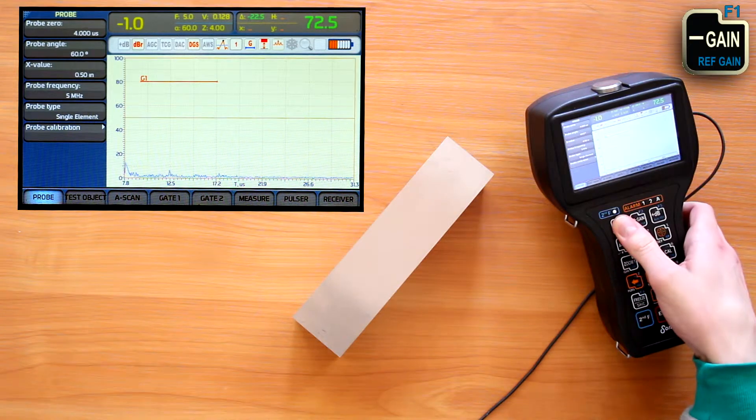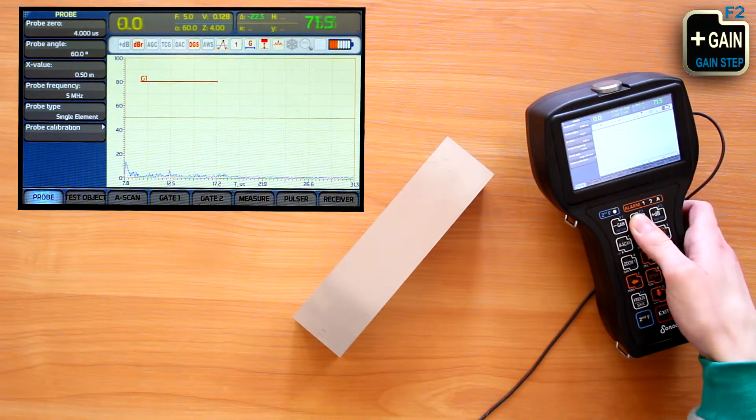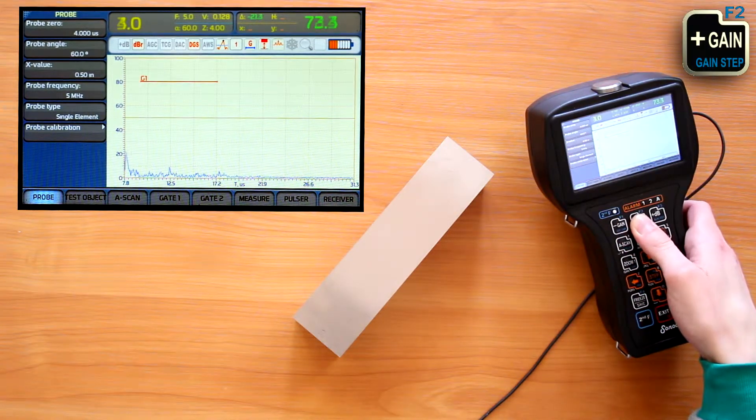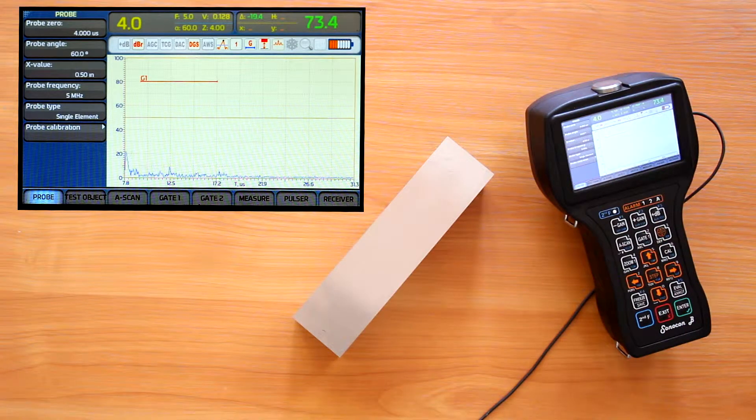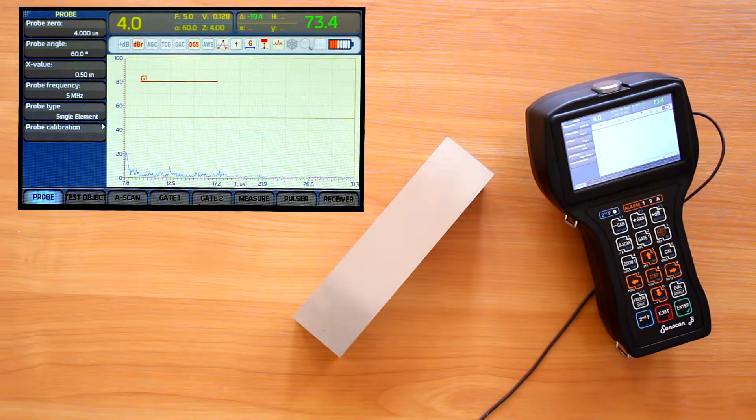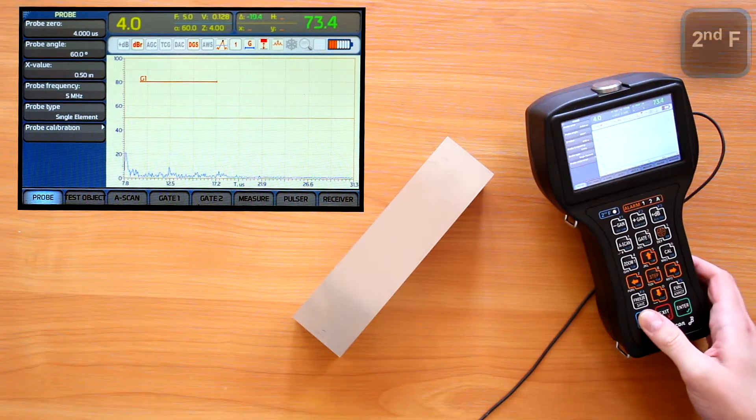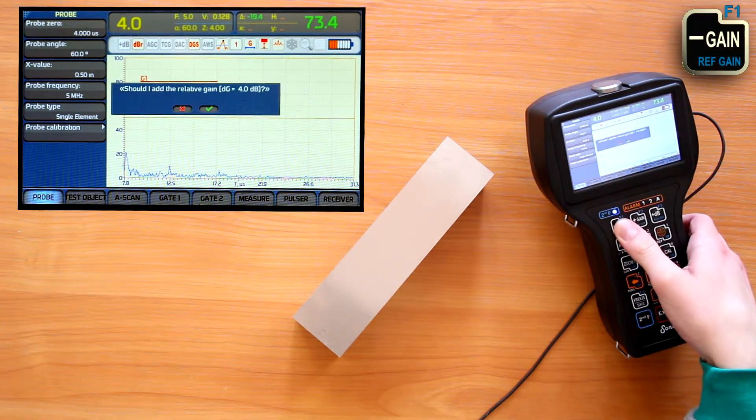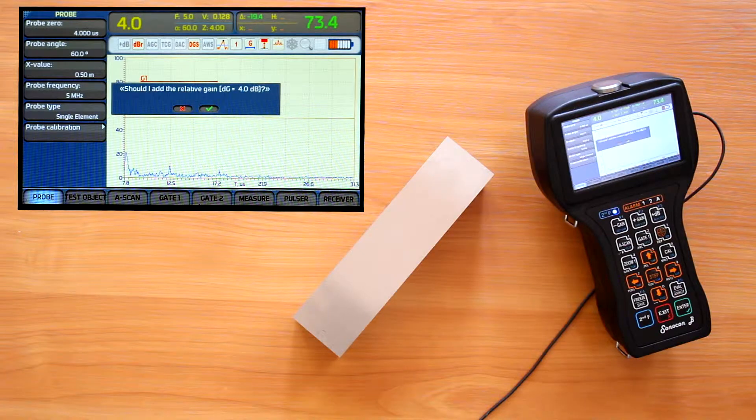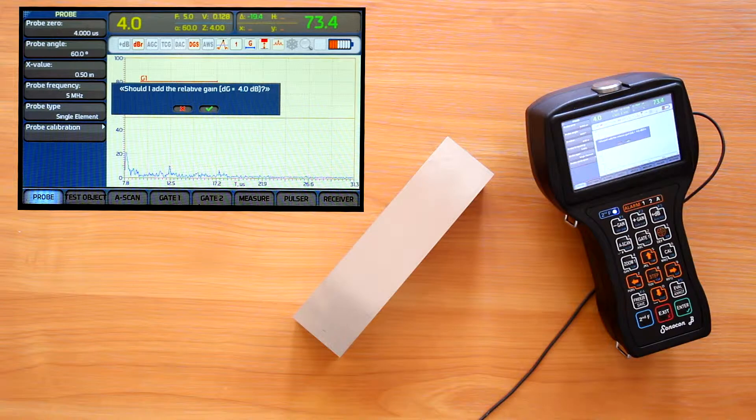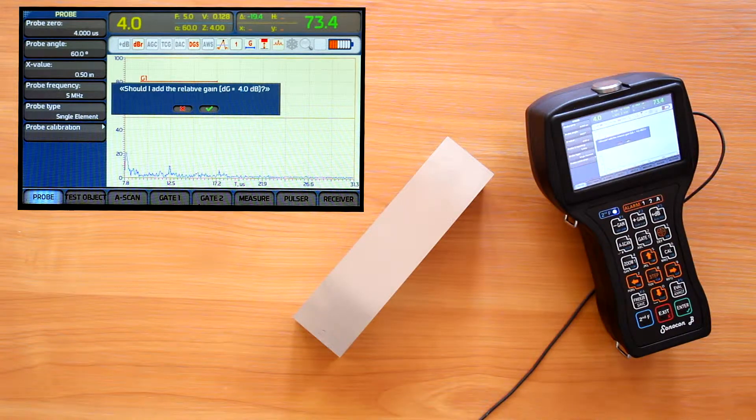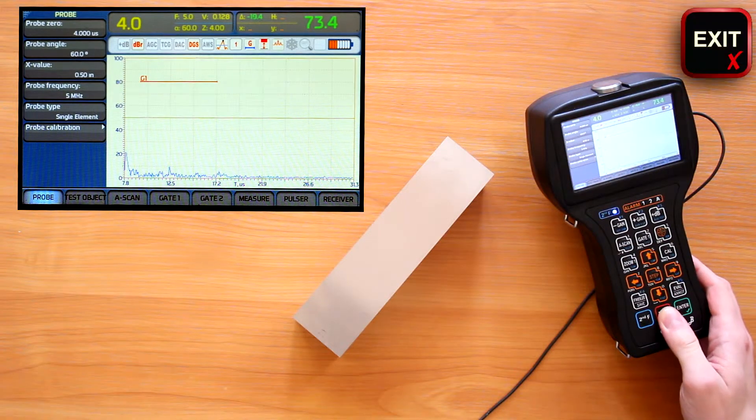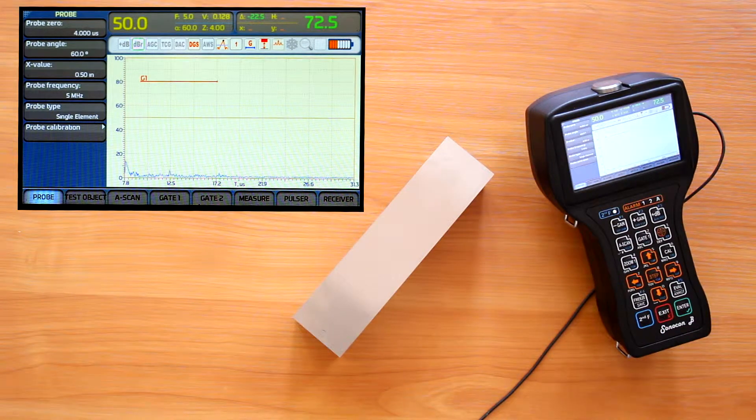Now we can change gain both up and down watching how it differs from the reference. When we try to turn the relative gain mode off with further press of second function plus gain minus, Sonocon asks us if we would like to keep or discard changes of the gain from the reference value. Pressing enter button we agree to keep the changes and pressing exit button we get back to the reference.